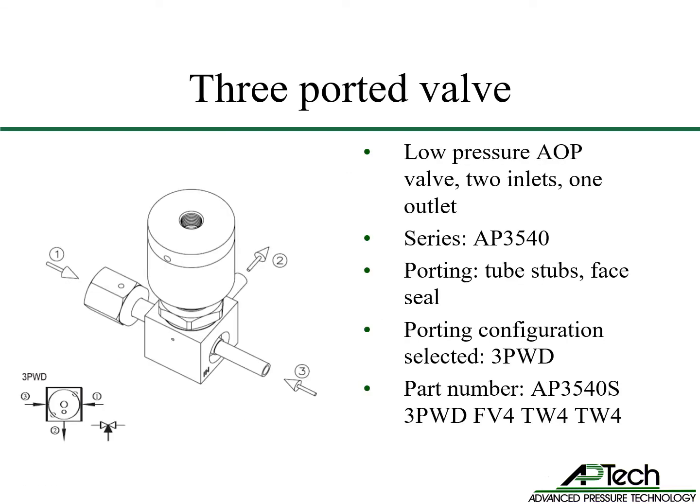The three-ported valve with two inlets and one outlet is a 3540 valve. The inlet port is quarter inch female face seal and flows through the body under the seat to the other inlet port with a quarter inch tube stub. The outlet port is opposite the inlet ports and is downstream of the seat. This is a 3PWD flow pattern. When configuring the part number, the ports are specified in sequential order starting with port number one. The part number is AP3540S3PWDFV4TW4TW4.